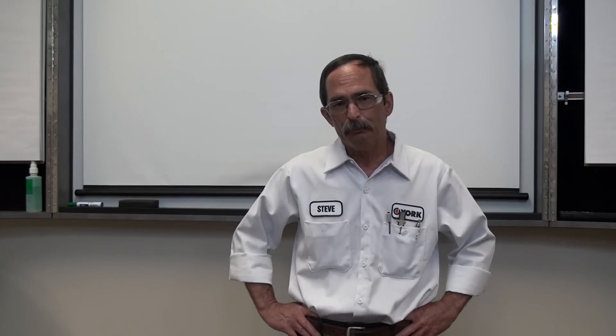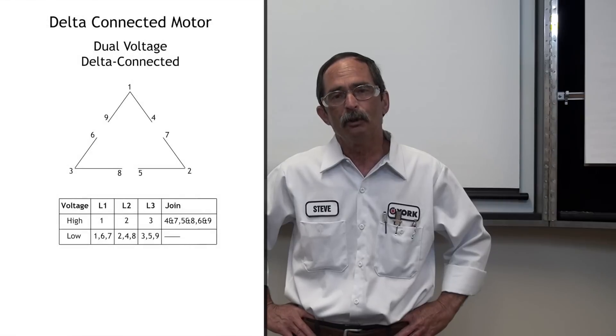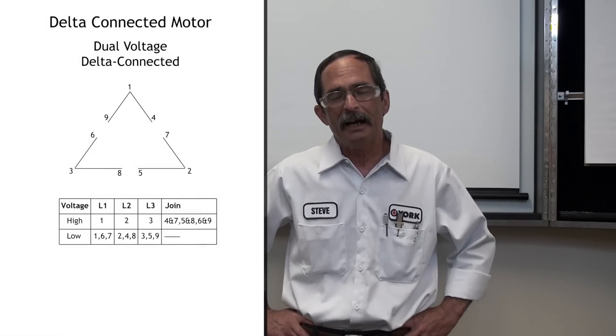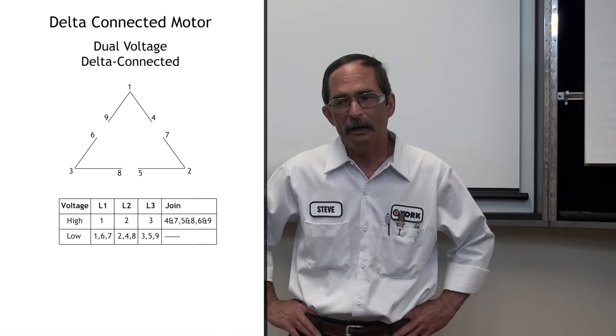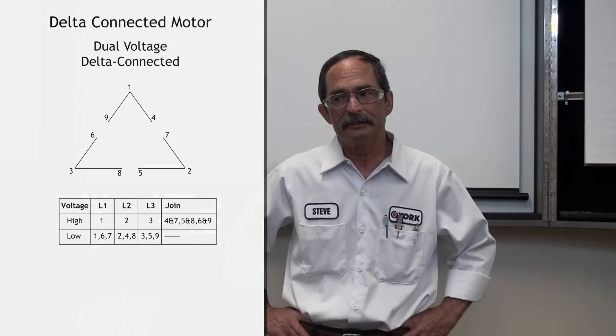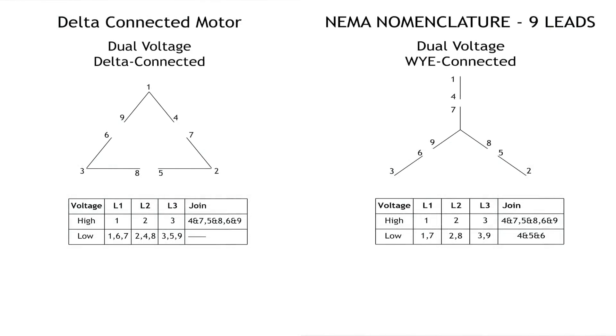If we end up with three combinations of three as we're checking continuity, then what we've got is a delta configuration, and that will change our high and low voltage connection. The high voltage connection, whether it's Y or delta, is going to be the same. The low voltage connection will definitely change. So we need to find out whether we have a Y or a delta configuration before we go ahead and wire it.